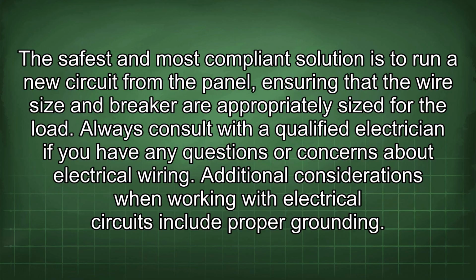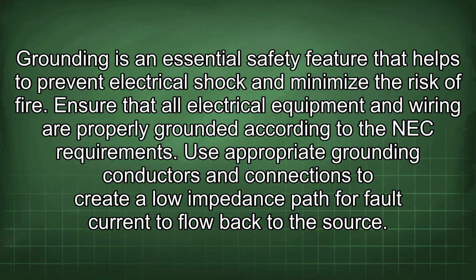Additional considerations when working with electrical circuits include proper grounding. Grounding is an essential safety feature that helps to prevent electrical shock and minimize the risk of fire. Ensure that all electrical equipment and wiring are properly grounded according to the NEC requirements. Use appropriate grounding conductors and connections to create a low impedance path for fault current to flow back to the source.